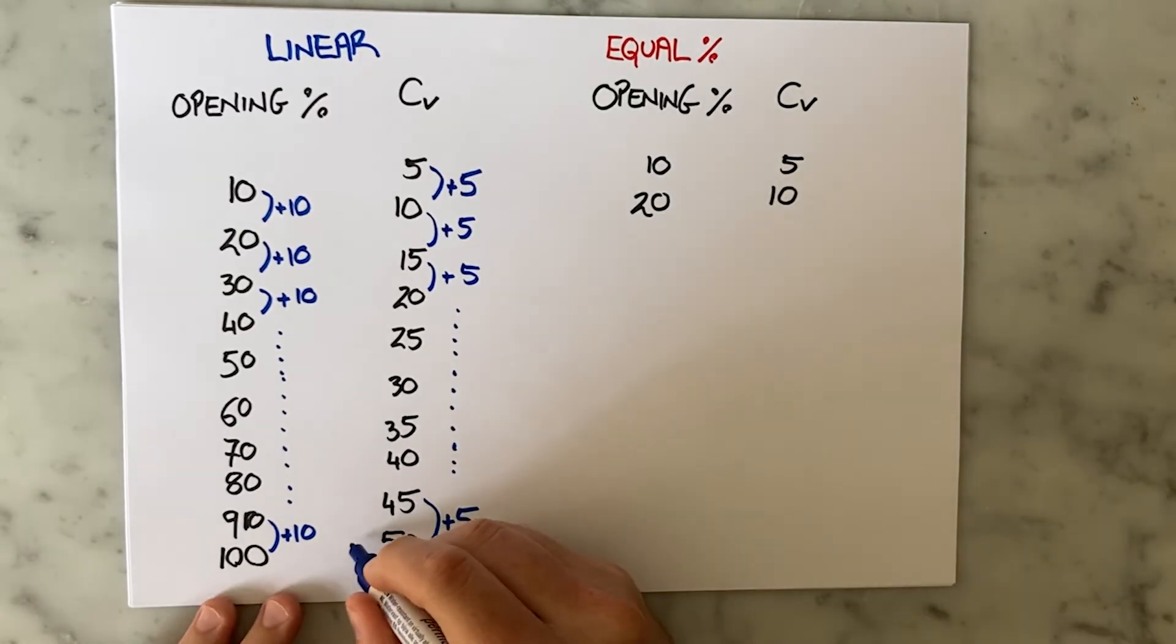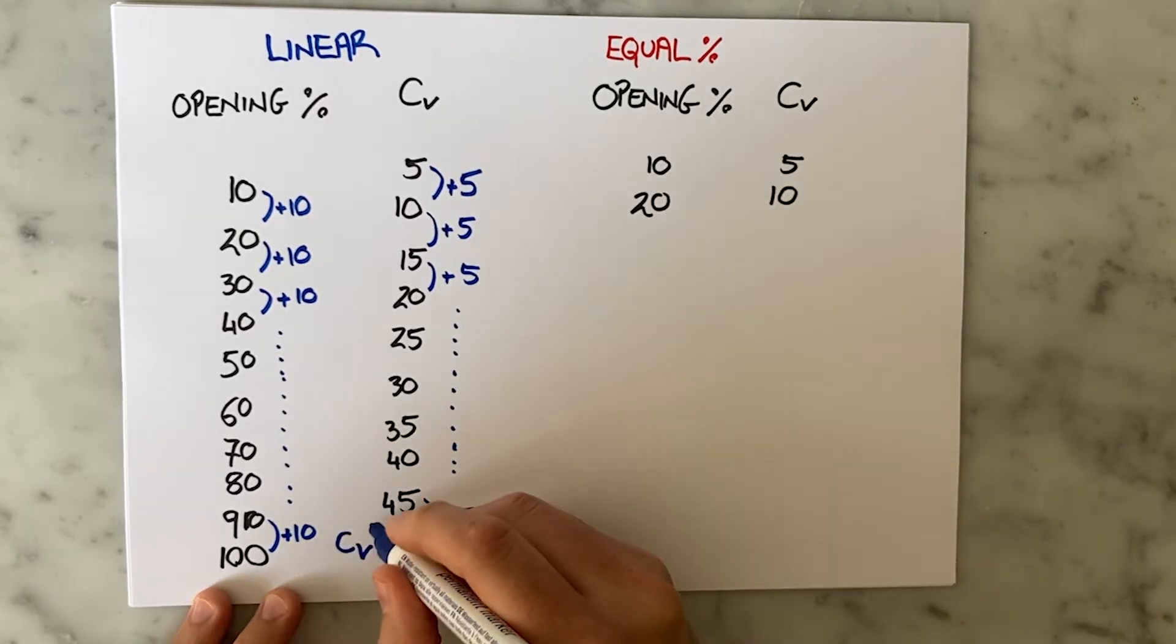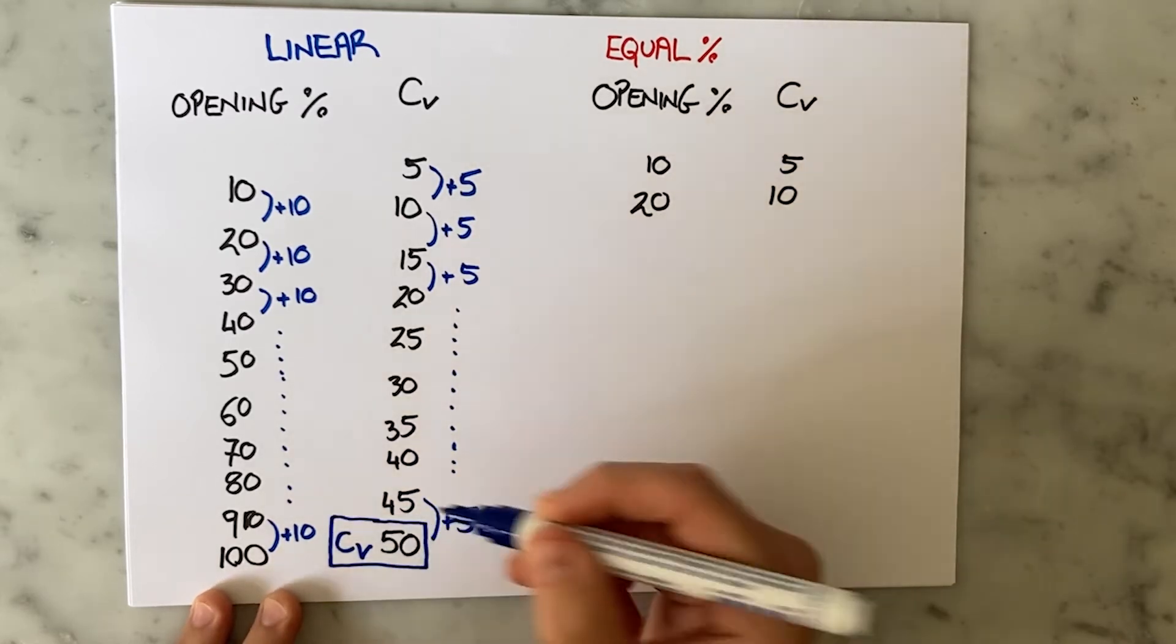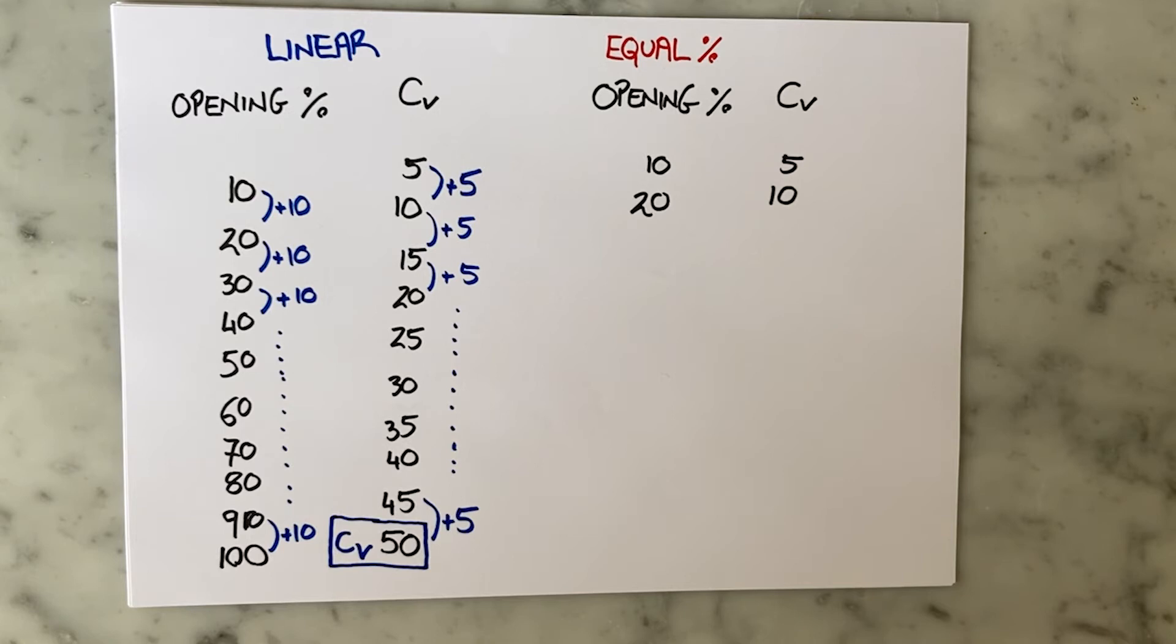The CV that is quoted on a datasheet is the 100% open or full bore CV value. So if you own this valve you would be the proud owner of a CV 50 valve with a linear characteristic.